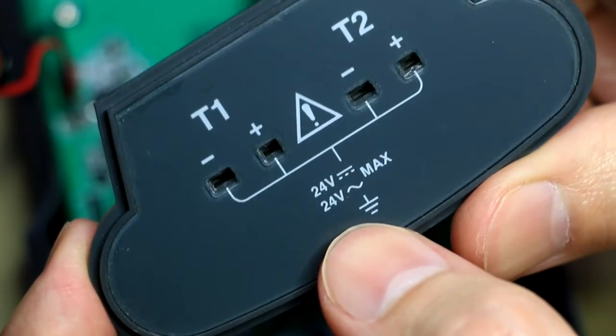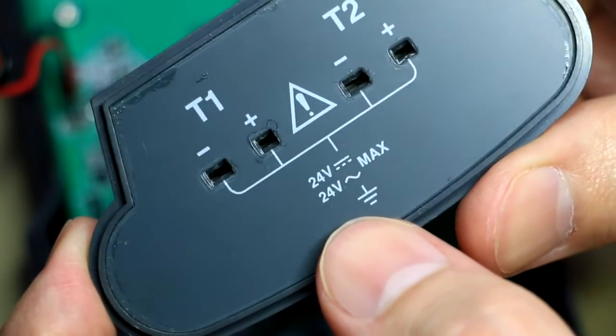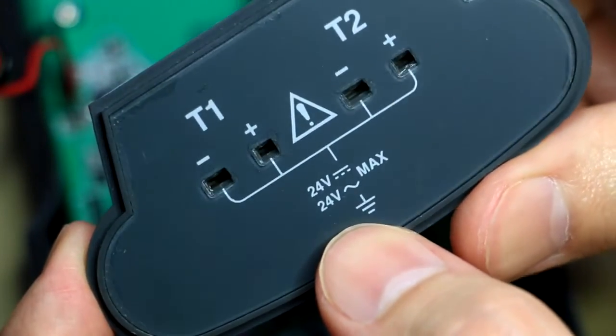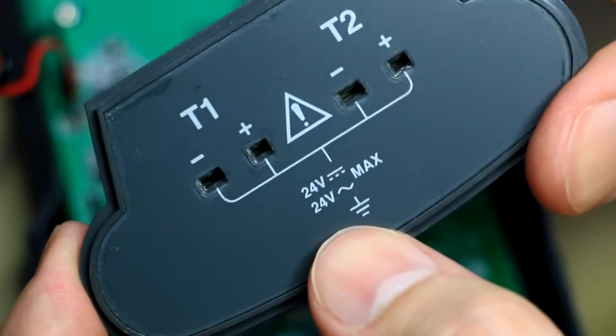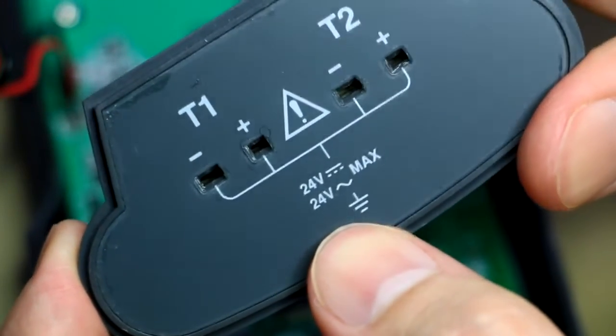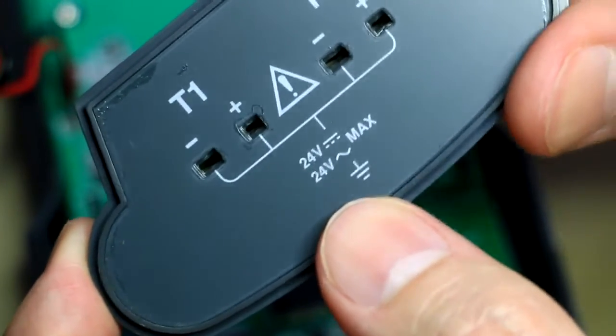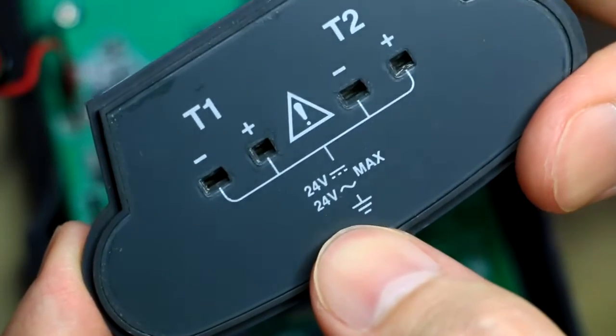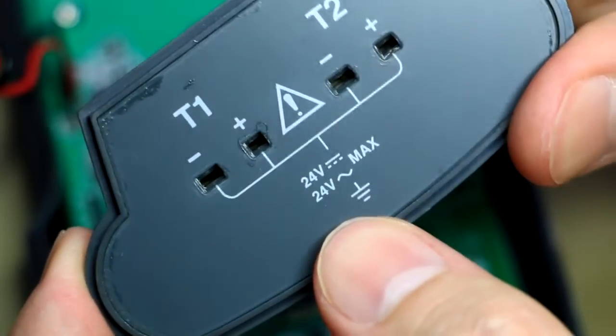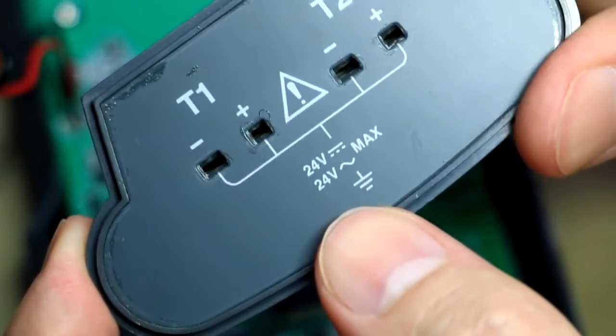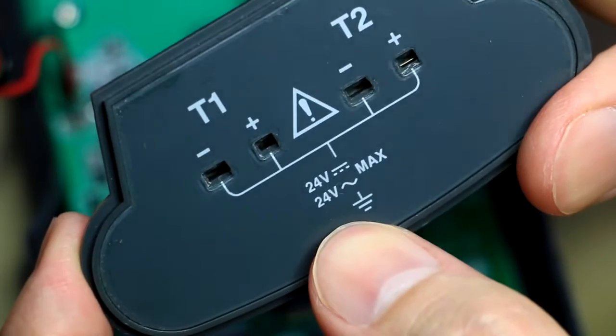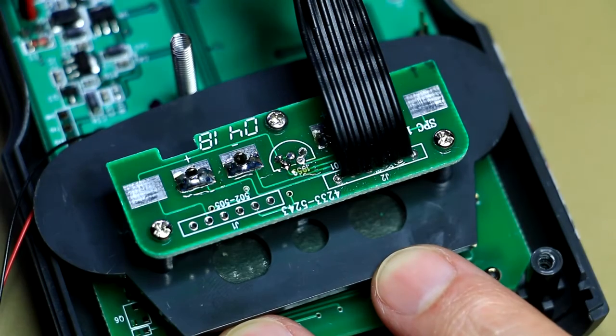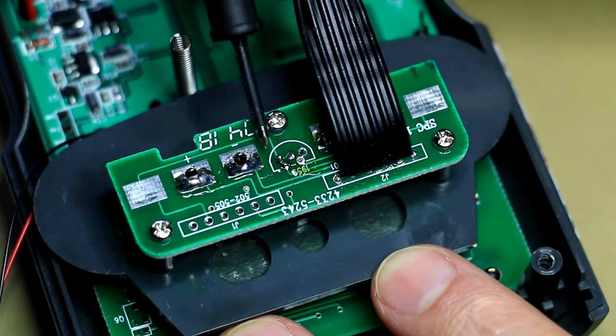two probes definitely damaged this instrument. I want to actually show you on the inside of this connector—it's got cold junction temperature compensation. And if you don't know what that is, I'll link Dave Jones' excellent video on temperature probes just down below.